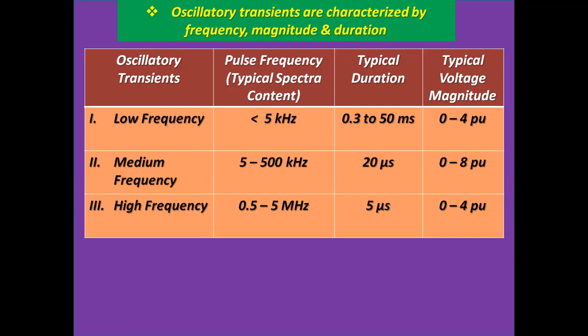Oscillatory transients of medium frequency is 5 to 500 kilohertz. Typical duration is 20 microseconds. Voltage 0 to 8 per unit. Number 3, oscillatory transients of high frequency, that is 0.5 to 5 megahertz, 5 microseconds duration, and voltage magnitude is of 0 to 4 per unit.